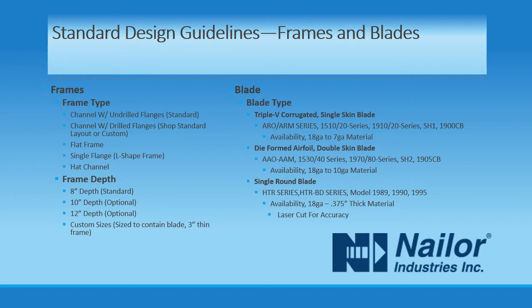For blade types, there are three common types suited to particular applications: V blades, airfoils, and single or butterfly blades. V blades are of a single thickness that can vary in response to pressure and flow requirements, with thicker blades able to handle more static pressure and airflow velocity. The main benefit of a V blade arrangement is economy of design and build — it uses less material and takes less time to build than an equivalent airfoil blade. Airfoil blades are typically used when the demands of the system are more stringent. Being double-walled, they are intrinsically stronger than the single-walled V blade and tend to maintain their shape under severe pressure and flow without warping.